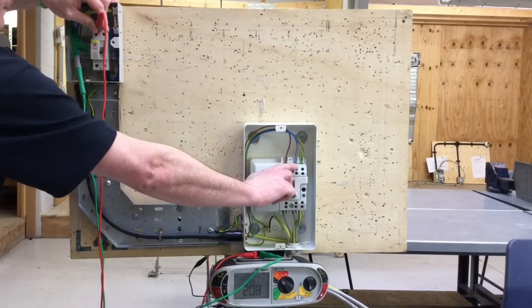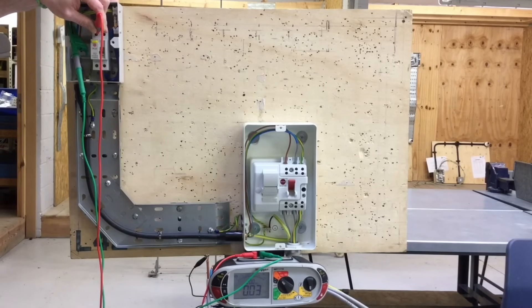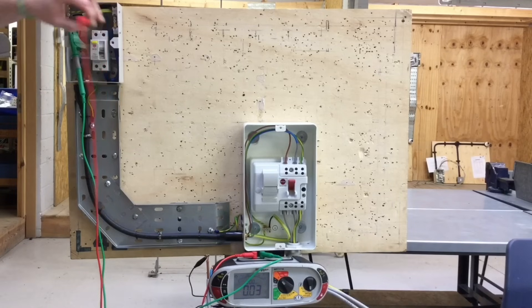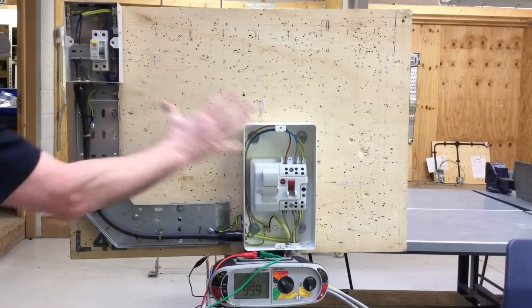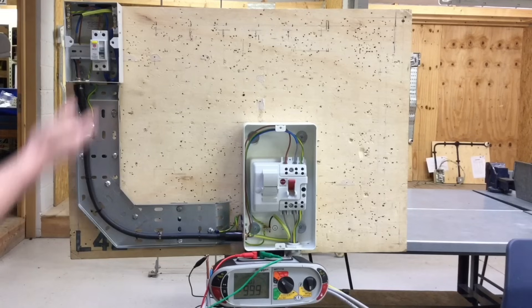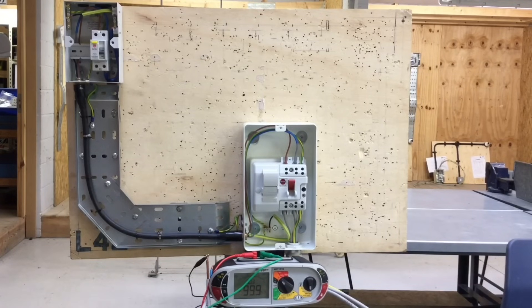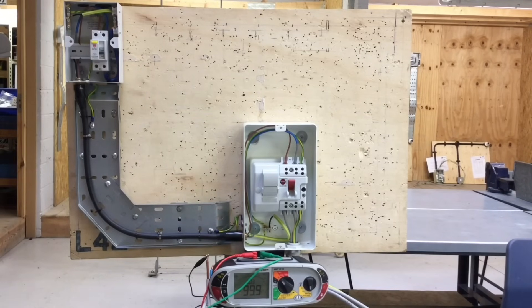Again, I can prove polarity by operating the switch — we see the circuit go off. As it's a double pole switch, both line and neutral are operated. We pull the fuse, circuit goes off, and we reconnect. By doing the test in two stages — first with the disconnected conductor for R1 plus R2 continuity of CPC and polarity, then with the parallel path reconnected — we prove polarity and confirm conductors haven't been mixed up. We record the highest reading of 0.06 ohms, prove polarity by operating the switch, pulling the fuse, and confirming that green and yellow is the circuit protective conductor.